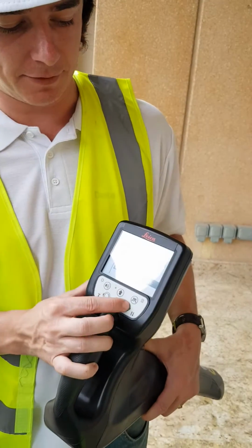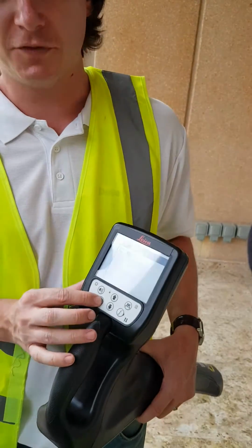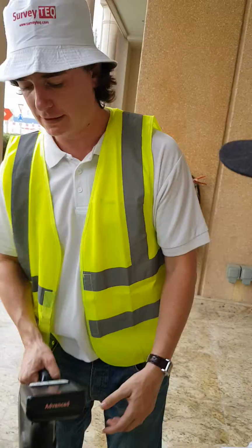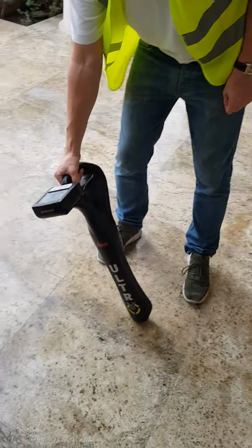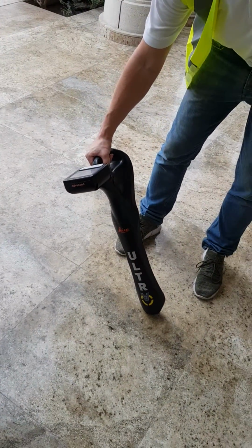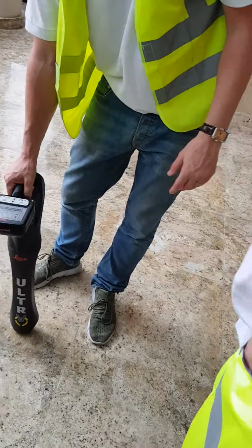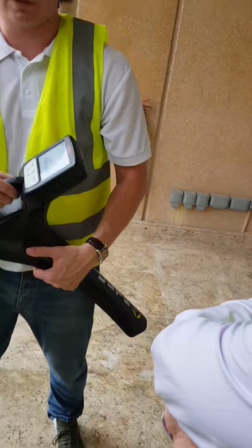And then offset depth. So this is on. Offset depth, if you remember, I said if you get to a cable and you can't quite find it, you can then rotate the locator to the side, and then it will show you where the cable is, this distance from here to here, and it'll tell you the depth at that point as well. Okay, so we'll go through that.